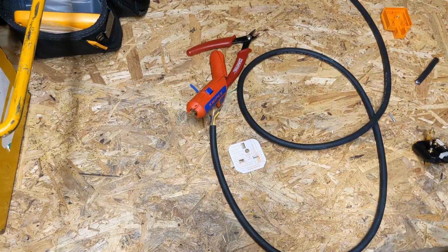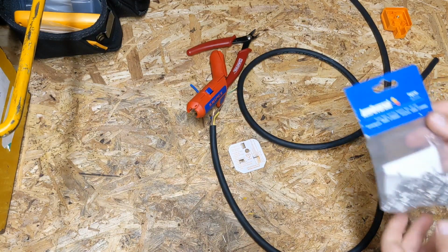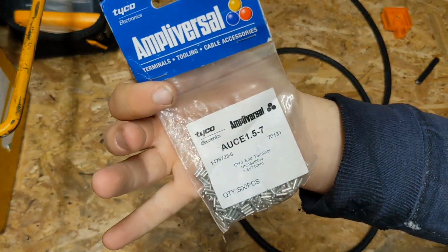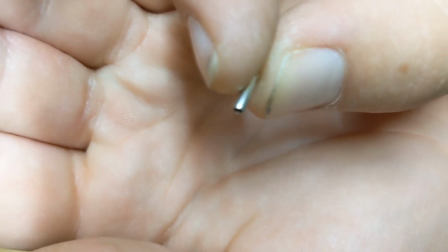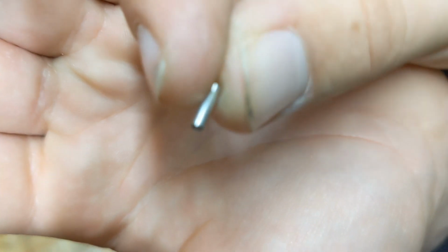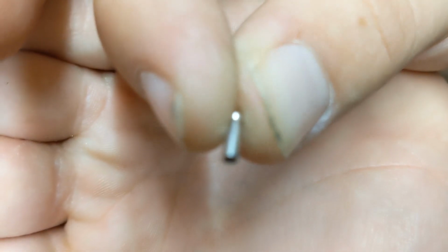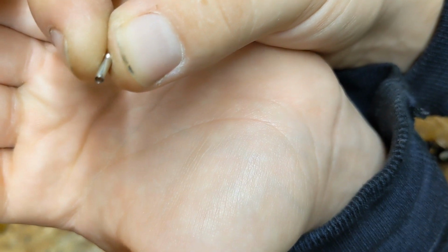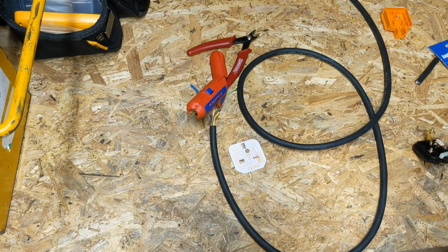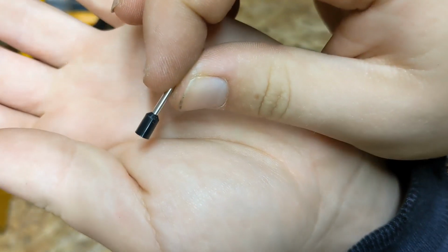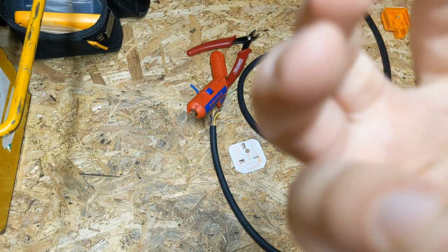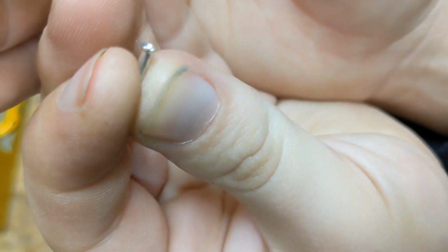Now, because we can, we're going to put some ferrules at the end, just to make it a little bit tidier. I use these uninsulated 1.5mm ferrules. All ferrules are like a copper tube with a tin plating on. What they basically do is take finely stranded conductors and make them into a solid strand, so when you tighten down on them, you don't break any of the fine strands. They come in very handy. You can get insulated ones as well, with colour coded shoulders, which could be used, but in 13 amp plugs there isn't really much room for ones with the shoulders on.